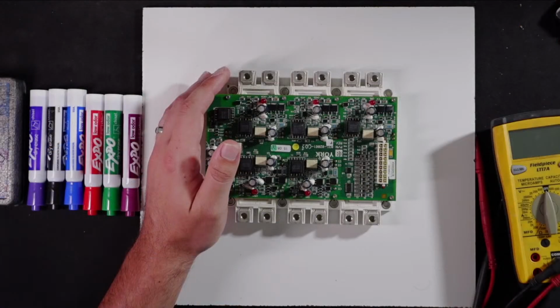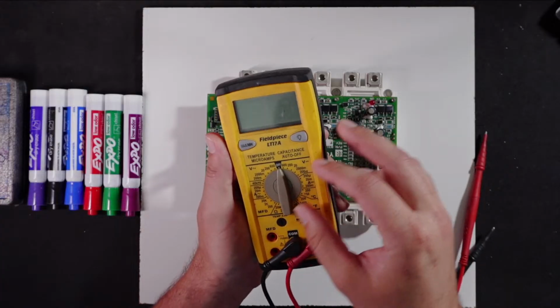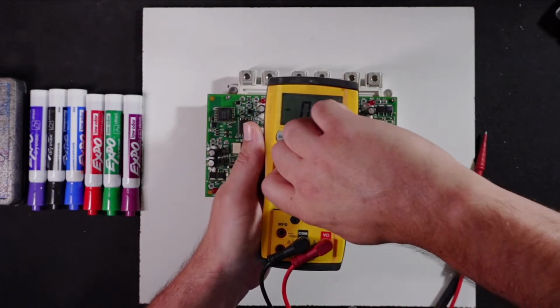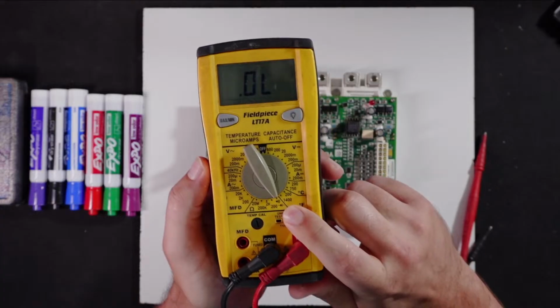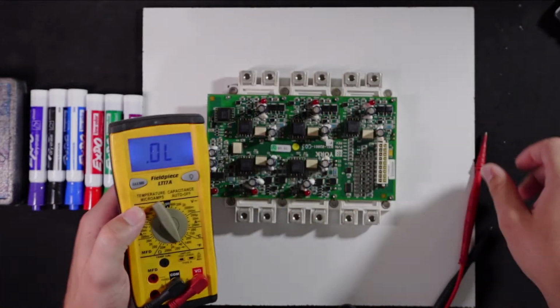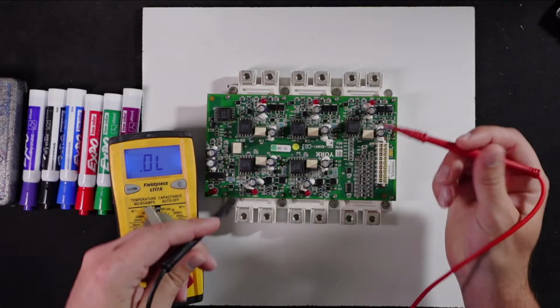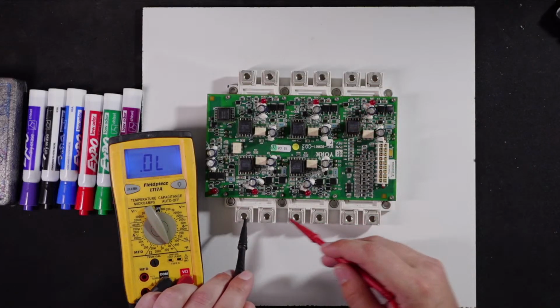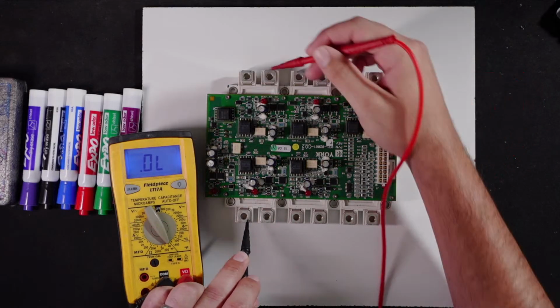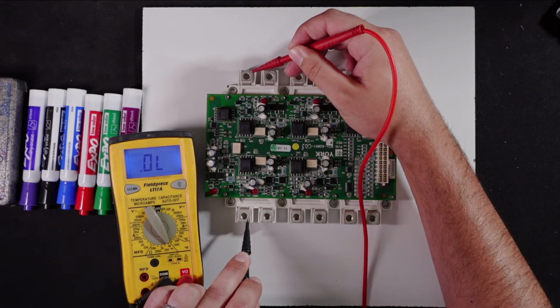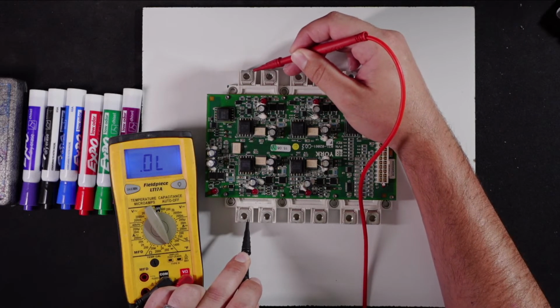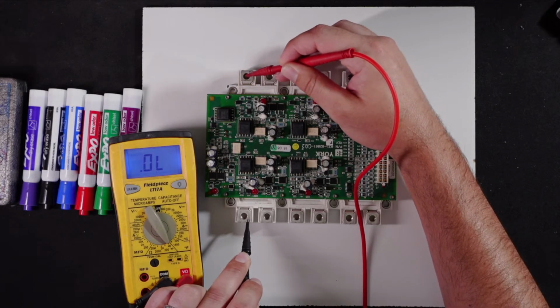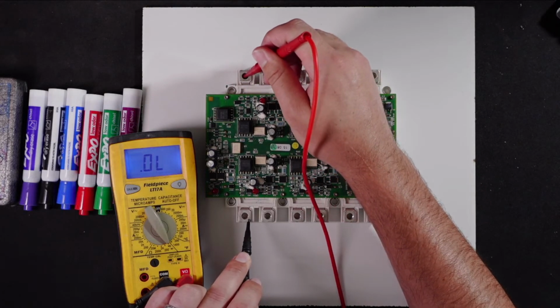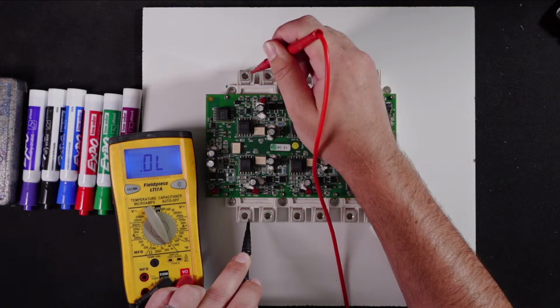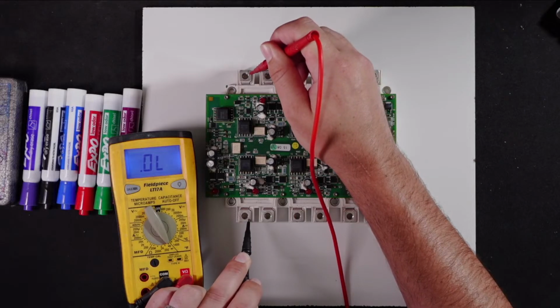One of the ways to test this is with your meter on diode. So that's going to be this little setting right here. We can measure across these. Now, this being my terminal 1, everything's going to come back to here. When you're doing stuff like this, make sure you're testing the actual pads, which is this part, not the threads. If I reach down in here and these threads aren't making contact with the pad, it's going to give me a different reading, or it could be a false reading. So make sure you're making contact with the pad.